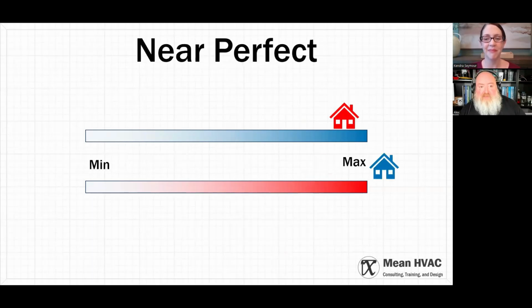If you're in Virginia, this will be near perfect. You size the thing and you're right up near the maximum on cooling, so on off days it can ramp down when it needs to, without being way oversized. You can still oversize these things, because if it lives down here, we don't know how it performs in a lot of cases, and it's dangerous. But you don't quite have enough heating capacity because Virginia isn't a hot climate—it's a green grass climate, a warm climate.